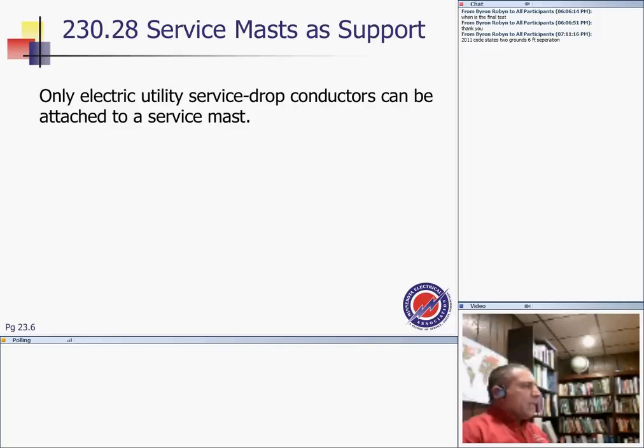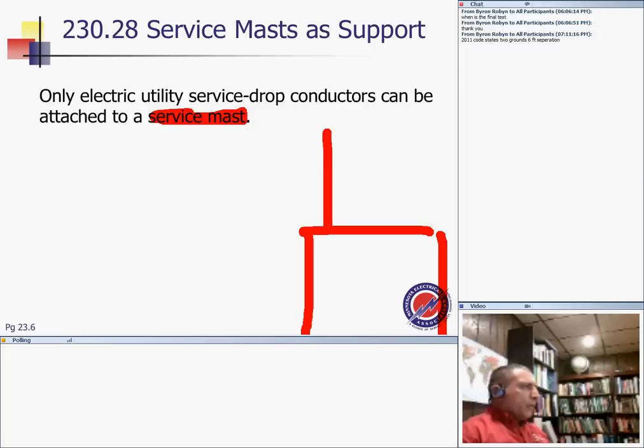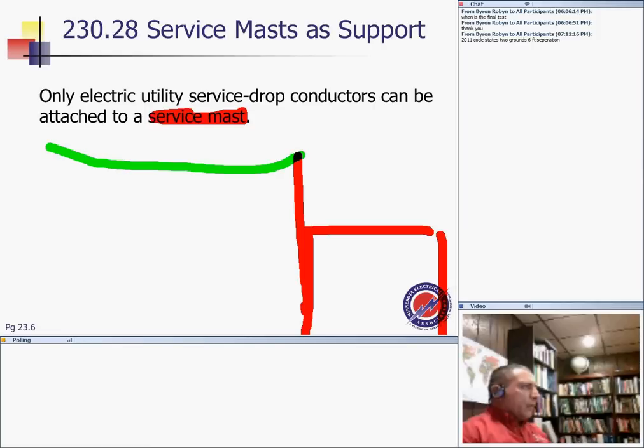Service drop conductor can be attached to the service mast, and we all know and have seen, guys, how the low voltage, the coaxial cable, go and tie to the mast. It should be right in this area here. There you go. So here's my mast, here's my power lines coming from here all the way down, and then the low voltage guys come and tie the low voltage line coming from here directly to the mast and bring it down. That's a no. Don't do that.